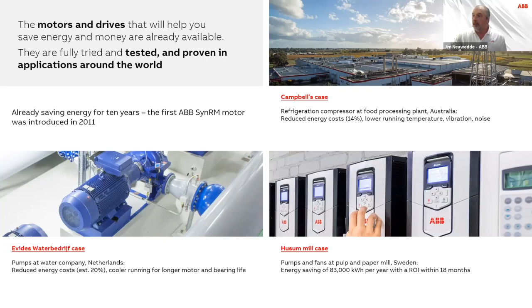So in short, anytime you have a pump or fan that doesn't have a drive on it, you're potentially losing energy. It's much more efficient to put a drive on a pump and fan and allow it to operate at the right speed, which will also save energy. A lot of times you've got mechanical dampeners involved, or maybe you're running it too aggressively, and if you ran at a lower constant rate, you'd actually save quite a bit of energy.